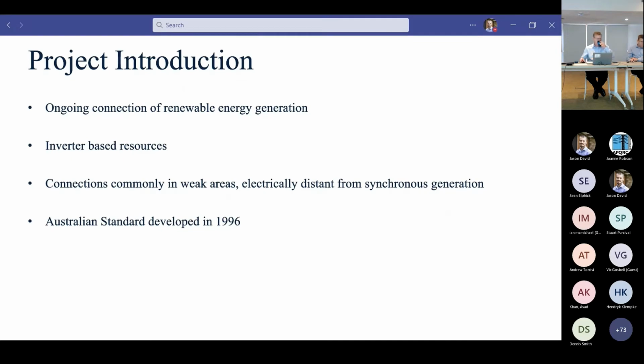We know there's an ongoing connection of renewable energy generation occurring, not just here in Australia but globally. By and large these are inverter-based resources: solar farm inverters, wind turbine generator inverters, battery inverters, HVDC, all sorts of things. These connections are commonly occurring in fairly weak areas, where the management of power system impedance may be more difficult, and being electrically distant from synchronous generation, which is capable of sinking harmonic currents and keeping voltage distortion to a reasonable level.